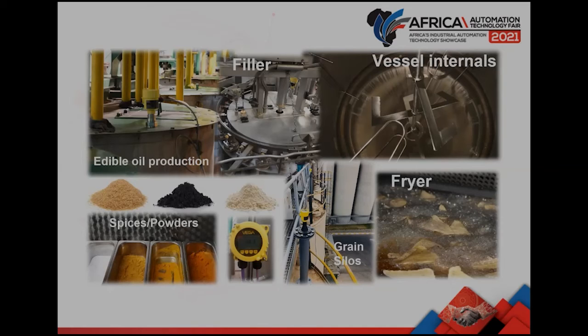We've got edible oil production, which is a typical application where you would find buildup, meaning oil sticking to the face of your device, but our devices compensate for that as well. We've got a filler, which is generally small vessels requiring compact devices. We've got tanks or vessels with internals, such as stirrers, heating coils, and the likes. For this, we've got signal focusing, which allows us to still have accurate level measurement.